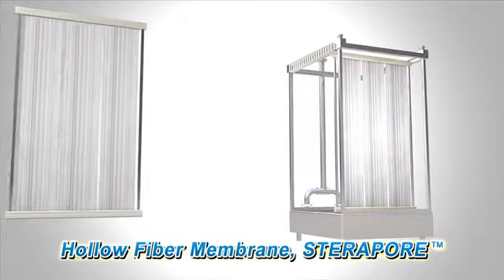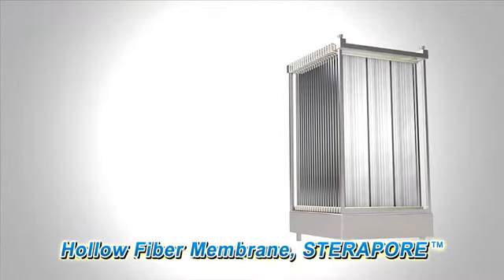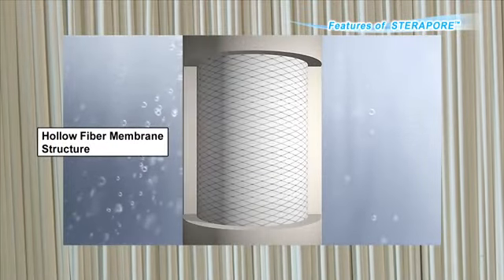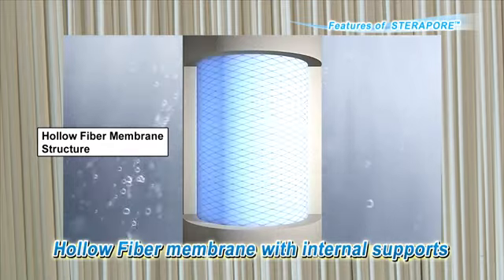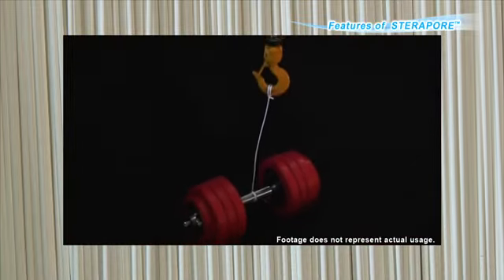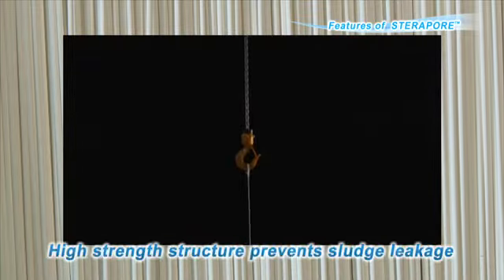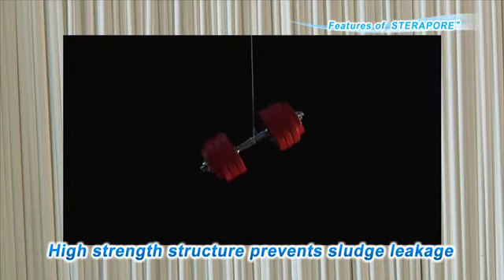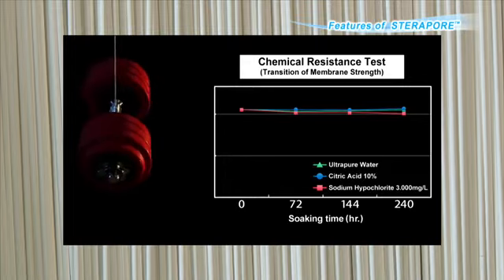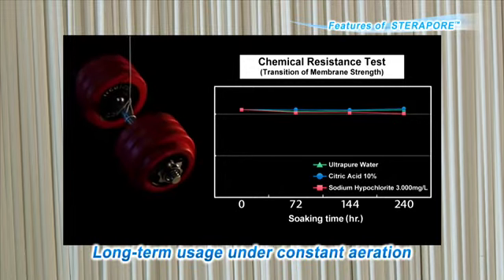Our PVDF hollow fiber membrane, Sterapore, has a design that allows simple operation, achieving a more space and energy efficient MBR system. Mitsubishi Rayon's hollow fiber membrane has adopted a structure with internal supports. Because this structure provides high strength, it can prevent sludge from flowing out to the treated water when unexpected damage or deterioration occurs. In addition to its high strength, it also has excellent chemical resistance, which allows long-term use under constant aeration.